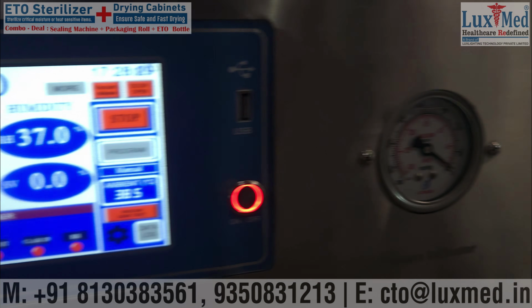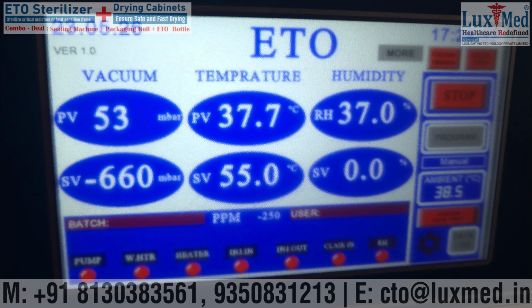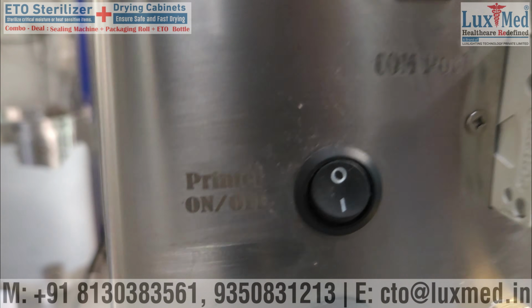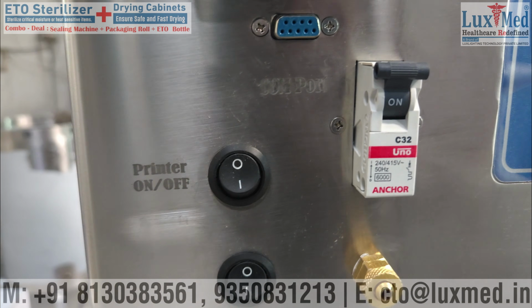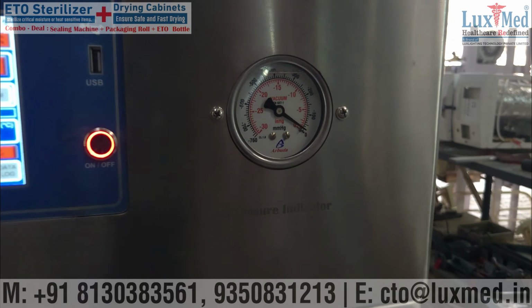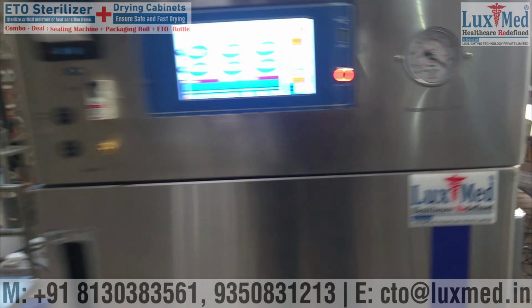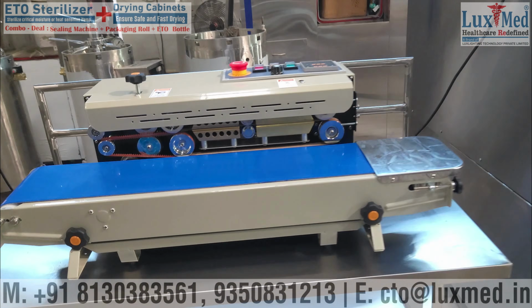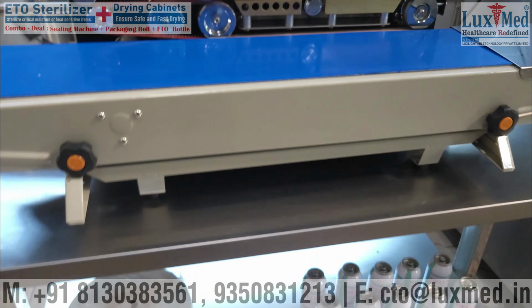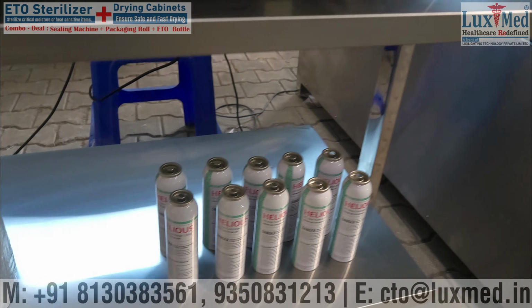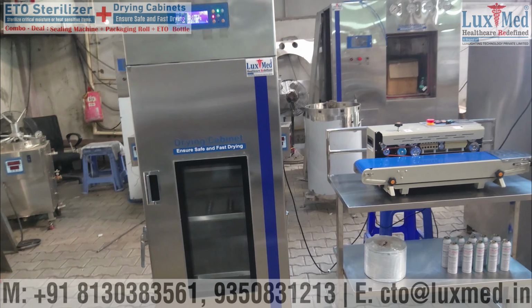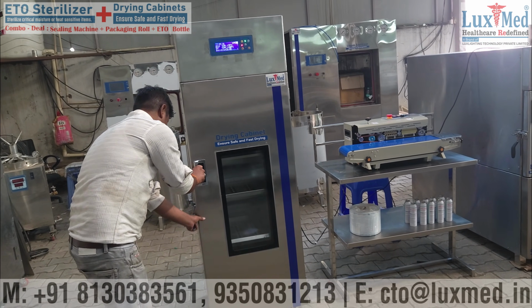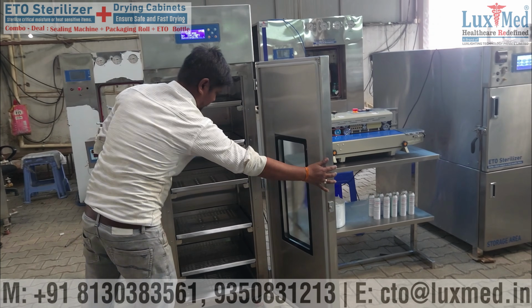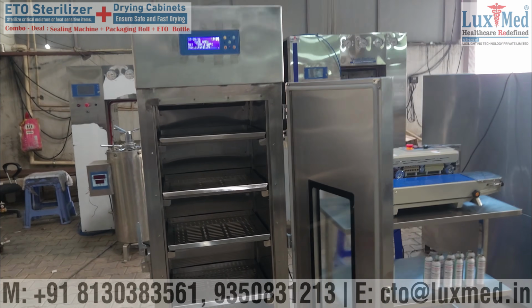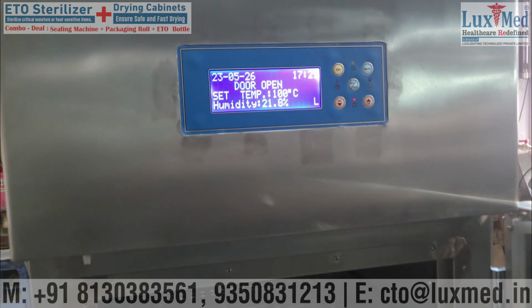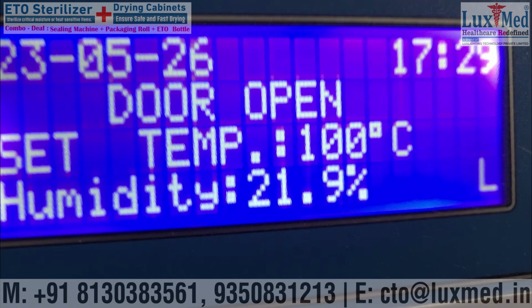How they work together in a CSSD workflow. 1. Cleaning. Surgical items and medical devices are thoroughly cleaned and disinfected. 2. Drying. These items are placed into the drying cabinet to remove any lingering moisture. 3. Packaging. Once dry, the items are packed and sealed in specialized, air-permeable pouches. 4. Sterilization. The packed goods are loaded into the ETO sterilizer, where humidity, temperature, and ETO gas act together to destroy microbes. 5. Aeration. The products are aerated to vent out harmful ETO gas, making them ready for clinical use.